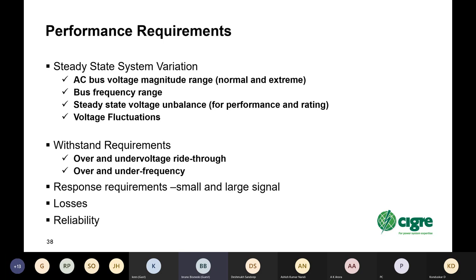And so typical performance requirements have to be demonstrated over the full bus voltage magnitude and range, maximum and minimum, or normal and extreme. Bus frequency range, again, up to the extremes, plus or minus frequency. Steady state voltage unbalance for filter performance and rating. Voltage fluctuations may be specified as well. It's flicker and voltage change on switching for cap banks and more filters.